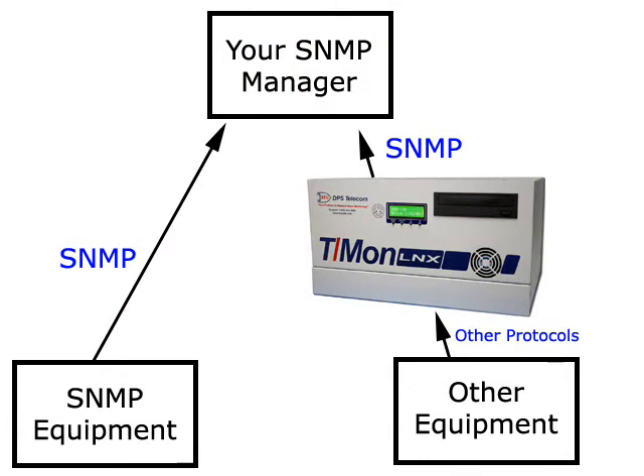Second, TMON can mediate non-SNMP alarms to your existing SNMP manager. Of course, you can send SNMP traps directly to your SNMP manager, but for non-SNMP gear, especially legacy equipment, you need an intelligent conversion device that will take in non-SNMP alarms, convert them to traps, and forward them to your SNMP manager. That's exactly what TMON will do for you in this application. When you add SNMP v3 capability, TMON can forward alarms securely to your top-level SNMP manager. The encryption offered by SNMP v3 makes all the difference at security-conscious organizations.